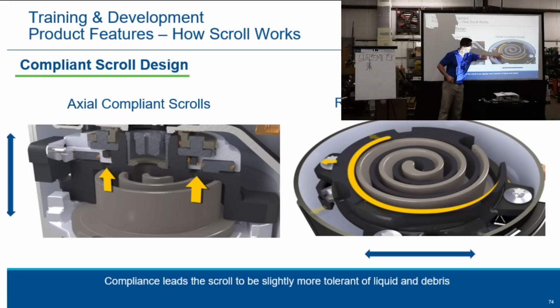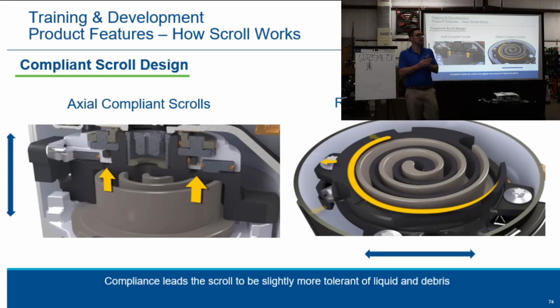These are called flanks. Right here, that's called flanks. That's what we call them, and they squish the gas together. But all of a sudden, if you get oil in here and it couldn't separate at all, you'll damage those. Right? Or liquid refrigerant, or debris, copper.